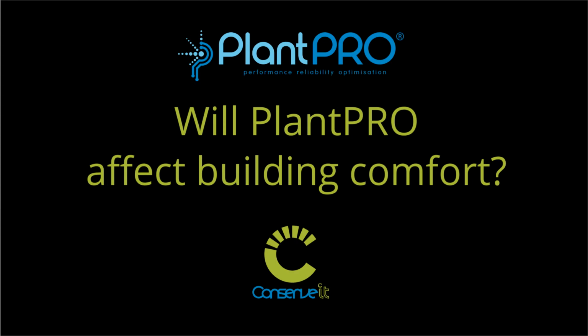Will PlantPRO affect building comfort? The short answer is no. PlantPRO's number one priority is maintaining building conditions and plant reliability. PlantPRO will stage the chillers, maintain the chilled water pumps and condenser water pumps, secondary pumps if they're present in the plant, and cooling towers, all within the acceptable limits of the chiller plants.